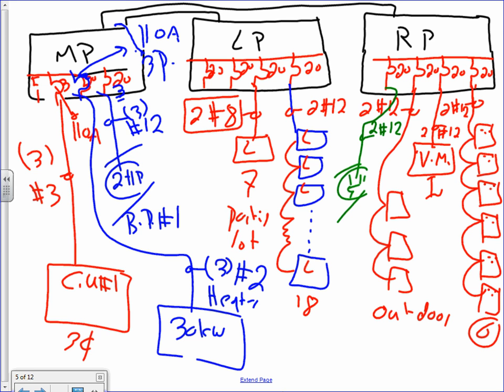In a receptacle panel, the receptacles in the counter in the office, no more than 6 in one circuit. When I say receptacle, guys, these are duplex or single receptacles. The quad counts as 2. Cool? So for receptacles, 6 on one circuit. Thumbs up? Cool. If it's a vending machine or any machine type, dedicated circuit. Then we go to the outdoor receptacles, throw 3 on one circuit in a commercial building. If you have another 3, throw them in another circuit. Okay? Exhaust fan, tiny little exhaust fan, put it in one circuit. Okay? Let's go to lights.